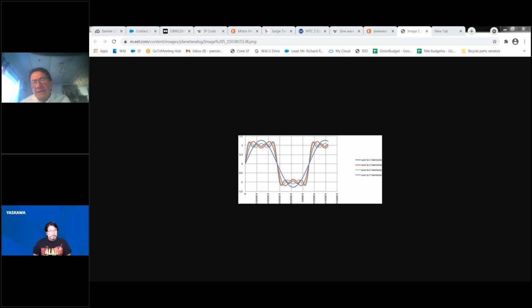But I think you understand the intent. So submersible motors were exhibiting much more problems than would be acceptable in any situation. And as we all started delving into it in the industry, the manufacturers, the distributors, the end users, Yaskawa, the other drive manufacturers, what we've understood to be the case now is that the submersible motors are not failing all the time on DVDT or voltage spiking issues in the windings. We're seeing a significant number of thermal failures.